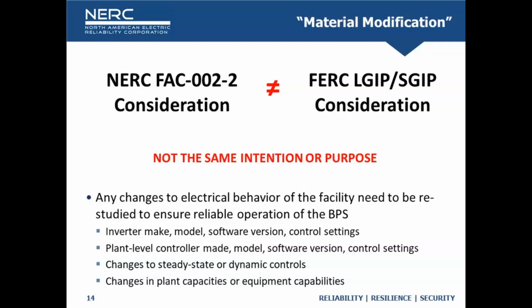And really what we've said is that any change to the electrical behavior of the facility needs to be restudied, because that's going to affect reliable operation of the bulk power system. So inverter make, model, software version, controller settings, plant level control modes, model, make, software version, control settings, any changes to the steady state or dynamic controls, changes in plant configuration, plant topology, plant capacity—all these things should be considered a material modification from the study standpoint, not necessarily the queue position standpoint.